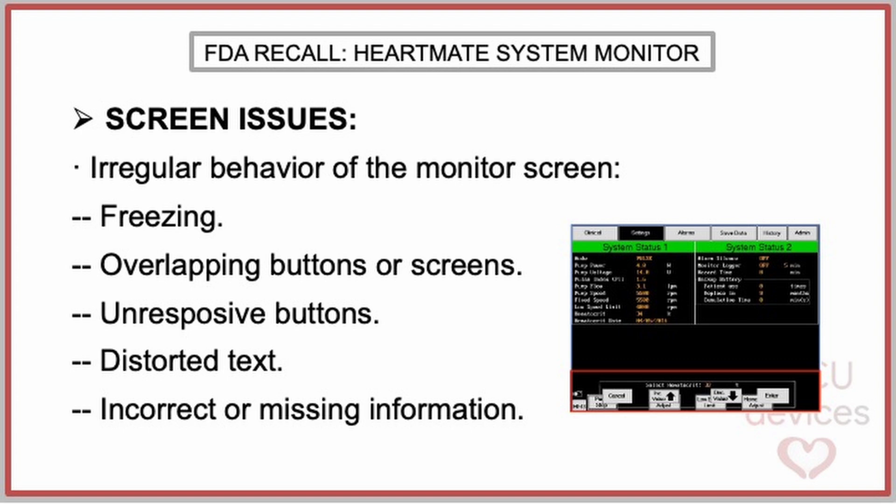The company has alerted about an irregular behavior of the monitor screen. These issues include screen freezing, overlapping buttons or screens, unresponsive buttons, distorted text or graphics, and incorrect or missing information on the display.